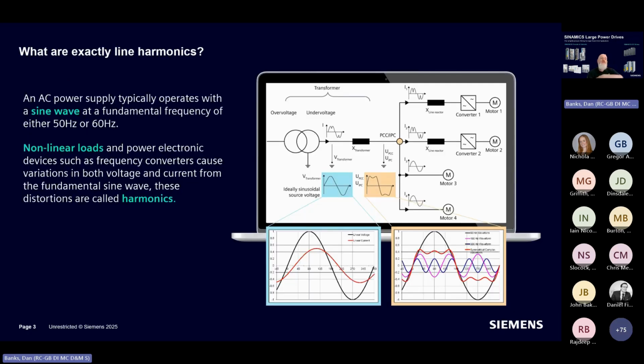So first of all, what are line harmonics? A basic take on this is that a standard AC power supply typically operates at a sine wave of 50 or 60 hertz - a nice, neat, perfect picture like in the blue box on the bottom left. Non-linear loads, like power electronics devices including drives, tend to distort them, causing variation in voltage and current from that sine wave - we call those distortions harmonics. The picture on the bottom right is a good indicator of the sorts of distortion types you might see from a variable speed drive.